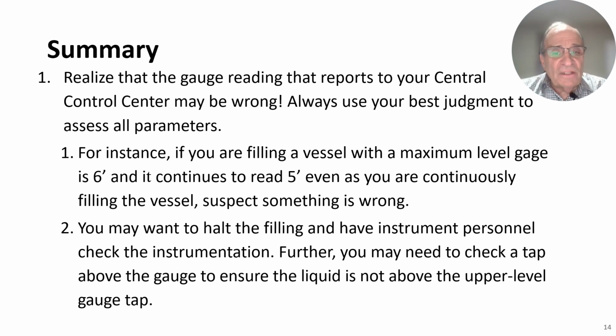For instance, if you are filling a vessel with a maximum level gauge of 6 feet and you keep filling it and it reads 5 feet, even though you're continuously filling the vessel, suspect that something is wrong. If it's staying at the 5-foot level and your maximum is 6 foot, that tells you that you're putting fluid into it and the gauge is not moving. You probably have a zero offset error in your reading.